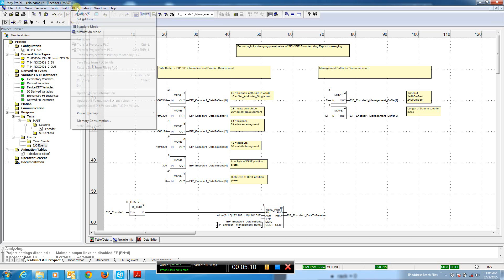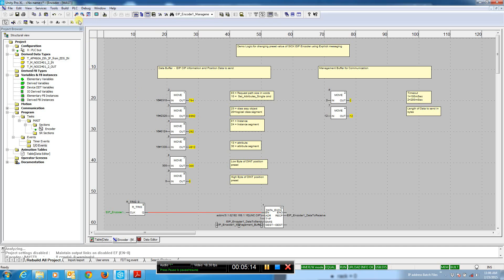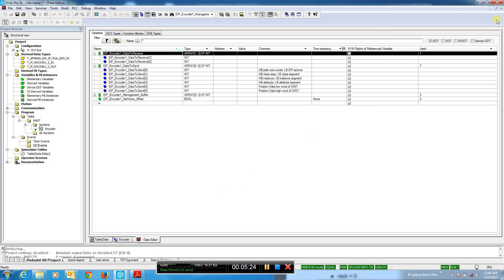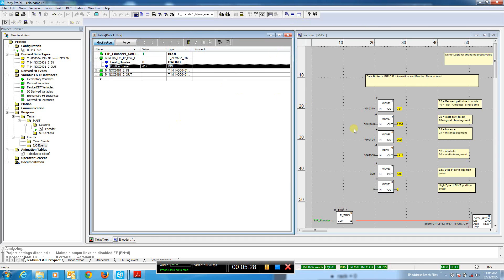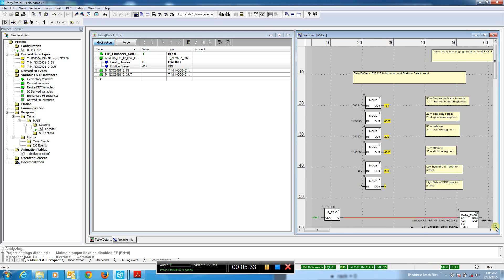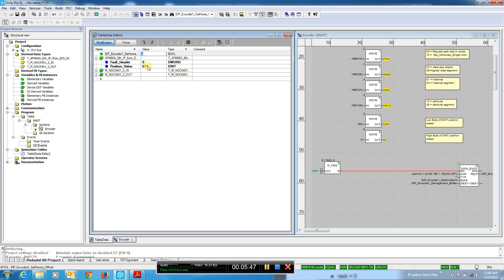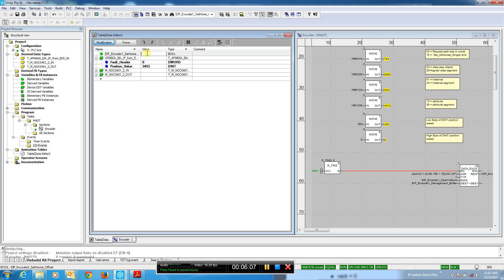I'm going to come in here — my system is already built — and do PLC connect. I am connected and already downloaded. I'm going to come over to my table and stuff the proper words in here. If I come to this trigger and turn that on, right now my encoder position value changes as I rotate it. I'll move that to a zero, then change it back to a one. You can see the position value change to 300. I'll change it again — it goes the other direction. I'll change it back to a zero, then to a one, and it goes there. If I want to change it to a different preset, I simply come into this register and change that, and that works.